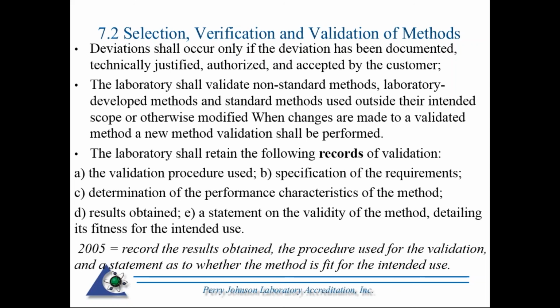The requirement in 2017 is you have to maintain records, and these include the validation procedure used, the specification of the requirements, determination of the performance characteristics of the method, the results obtained, and a statement of the validity of the method detailing its fitness for the intended use. So a lot more detail there as to what type of records need to be produced if you're validating.